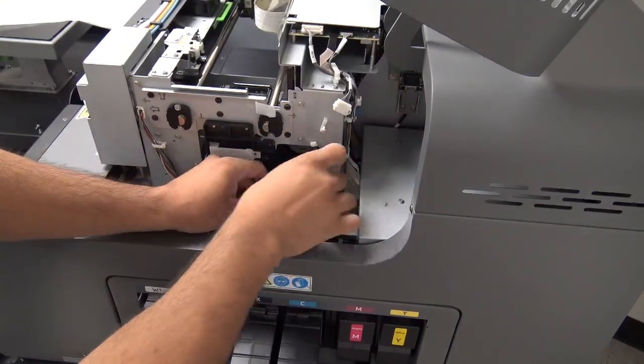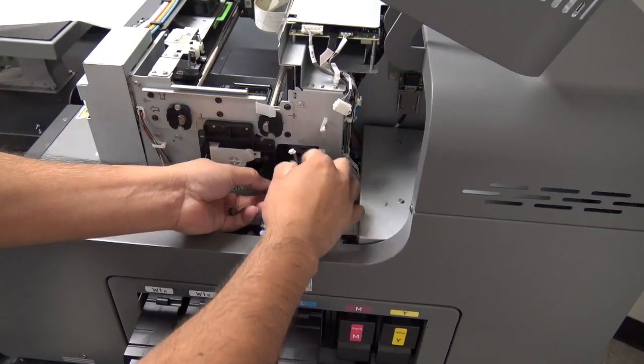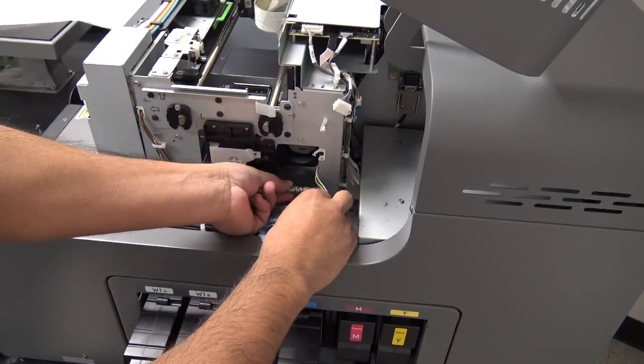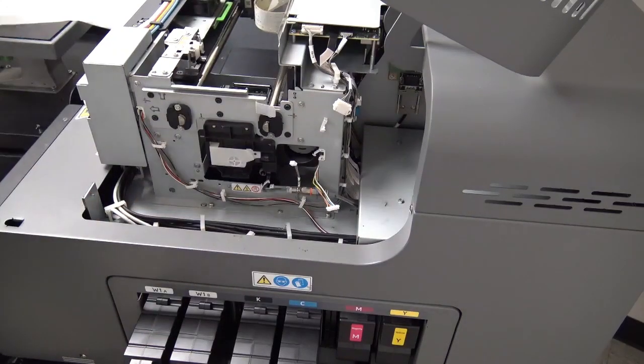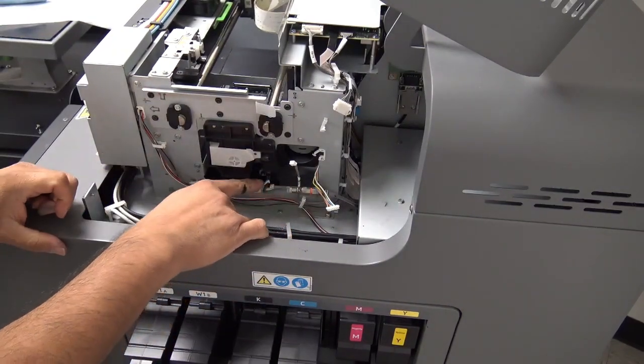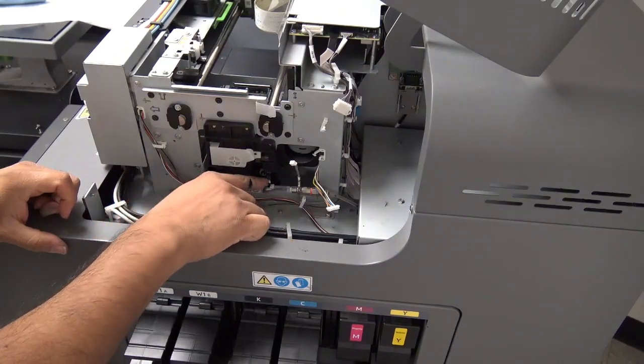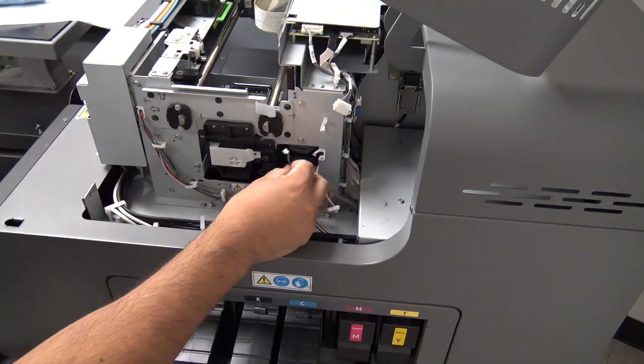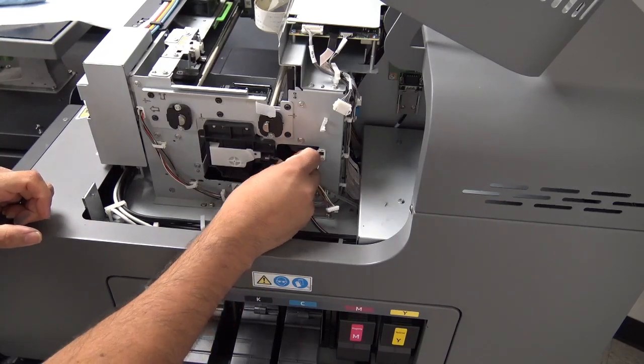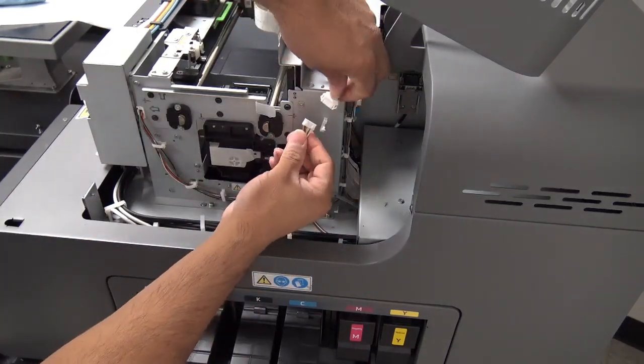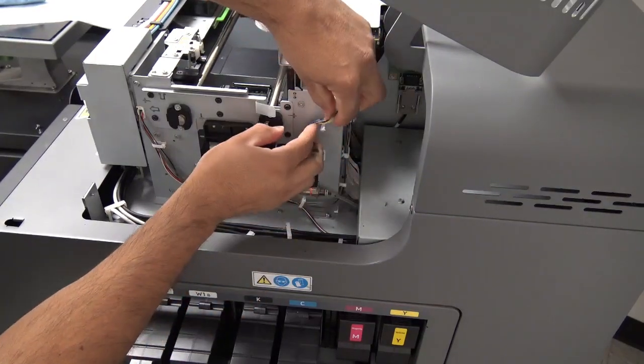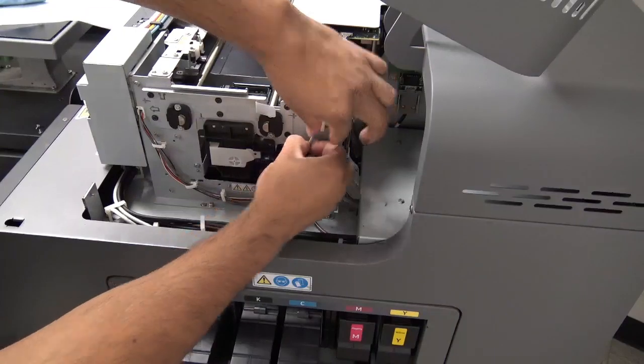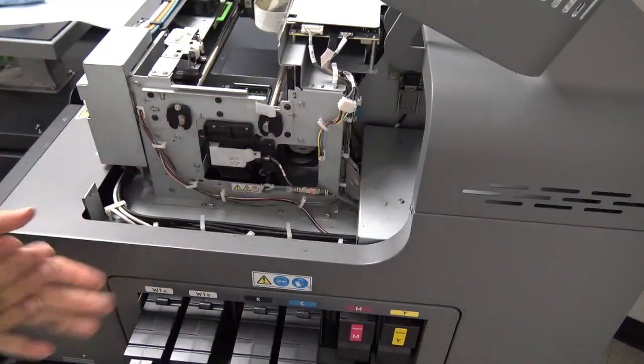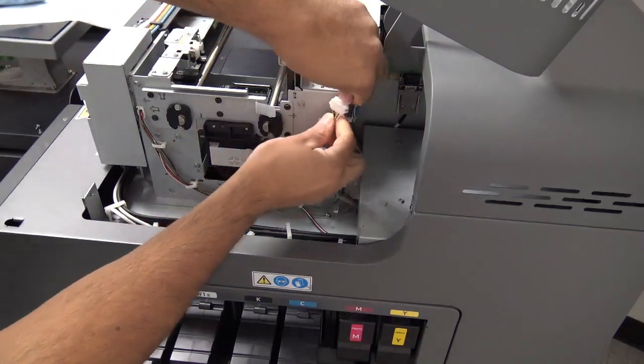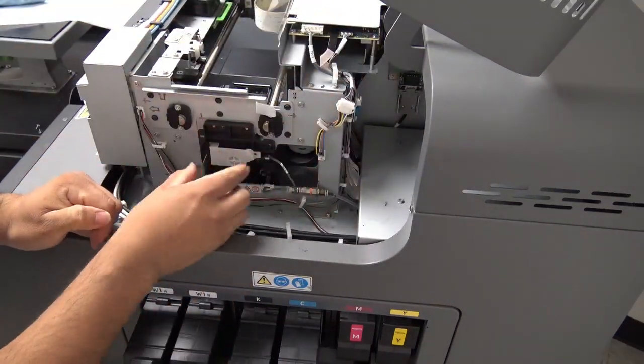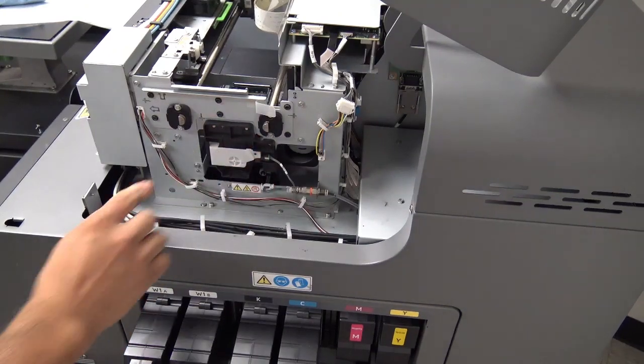There we go. I'm going to reconnect my waste valve here. To reconnect it, I push that back into that connection. We're going to make sure this tube here is not twisted or pinched. Once we make sure that's okay, we're going to close that little clamp there. We're going to reconnect our sensor power cable right there, and reconnect our drive motor right there. Going to make sure we close all these little clips back up. Okay, and we're just going to give it one more check. That's connected, waste valve's connected, sensor's connected. Make sure this is centered and stable right there, and we're going to put back our screws.